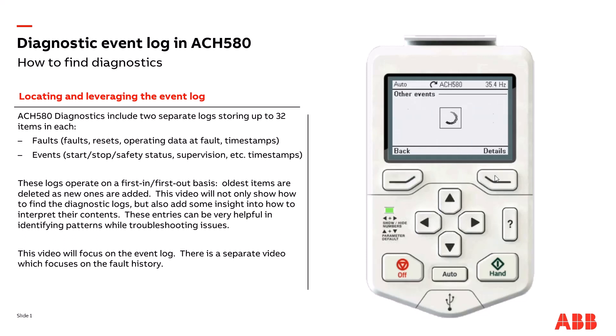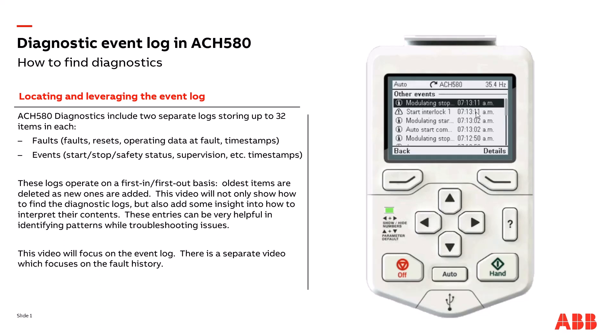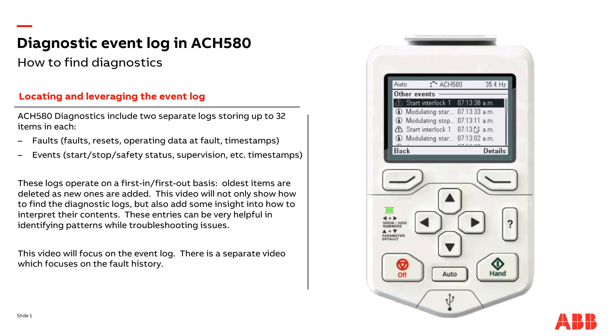Now we'll stop the drive and take a look at the event log. We can see Stop command and modulation stops. Now we'll start again, and this time I'm going to open up a safety while we're running. We get the interlock warning. Looking at the event log: modulation started, then the start interlock opened — and the timestamp is great here because we can see the whole sequence of operation.